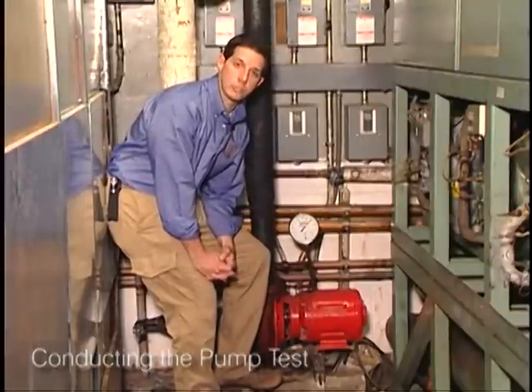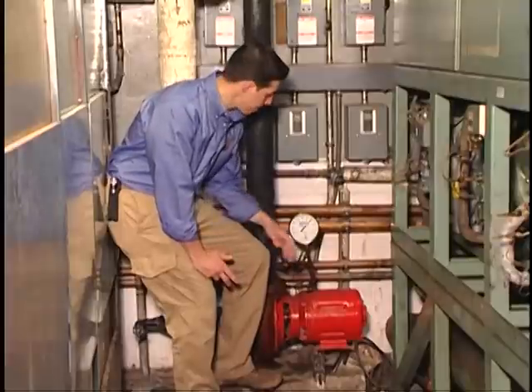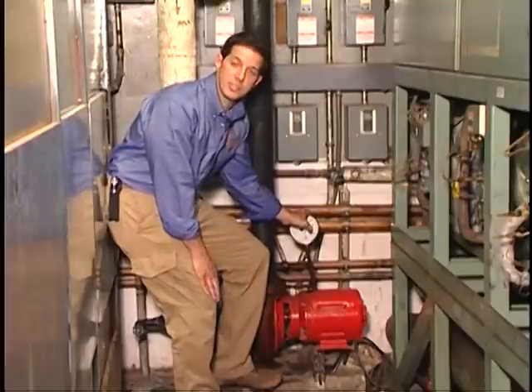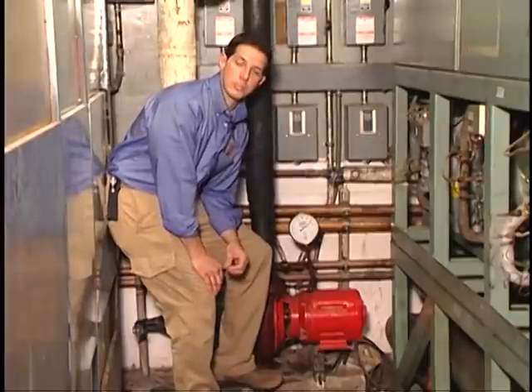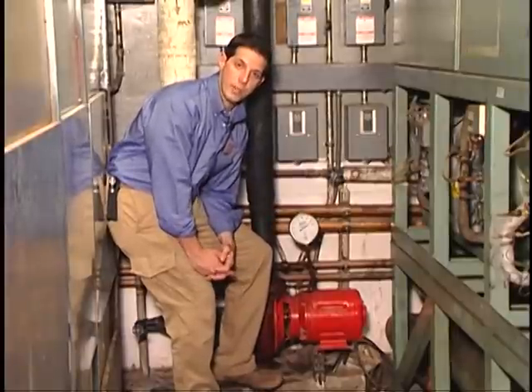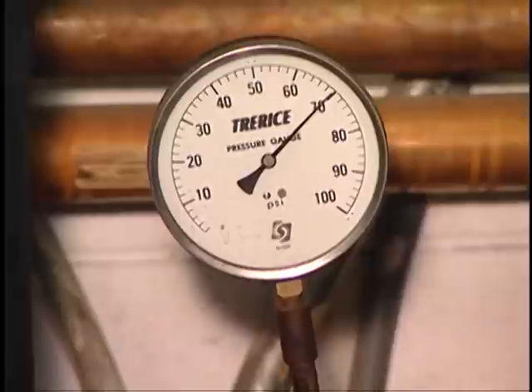We start with taking a flow utilizing an ultrasonic flow meter. We then, using a calibrated test gauge, take pressure readings. It's important to set up the pressure readings directly before and after the pump, as any instruments in between the pressure readings can affect our data.